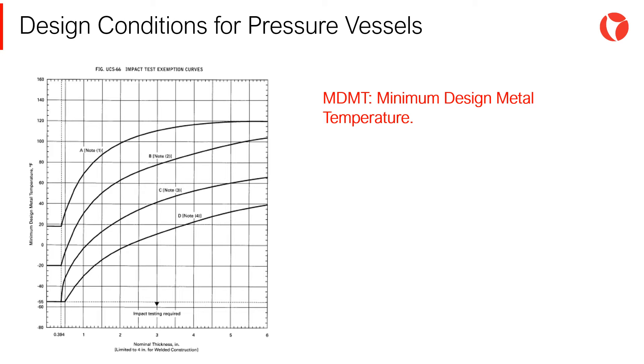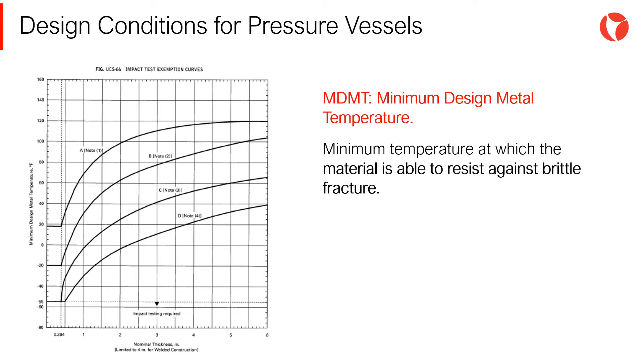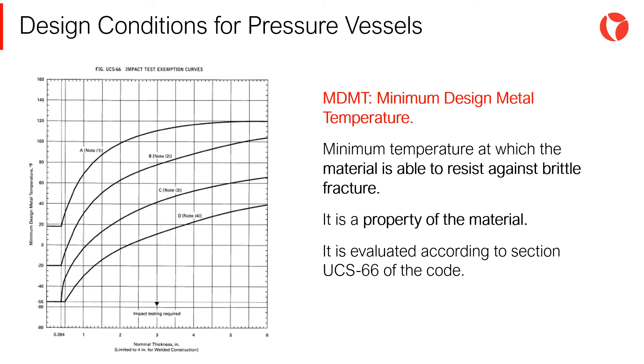Minimum design metal temperature, MDMT. It is the minimum temperature at which the material is able to resist brittle fracture. It is a property of the materials, and it is evaluated according to section UCS-66 of the code.